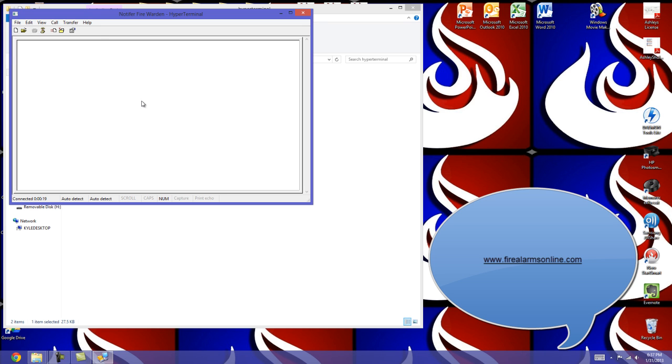And like I stated in other videos, once that's coming up, you can either pull an SLC loop off and get a whole description of all the devices that come into trouble, or if you're testing a building, as all these items come up, before you start you can go to capture text and save all this information to a text file directly on your desktop, so you can print it when you get back to the office or email it to a customer or another technician.